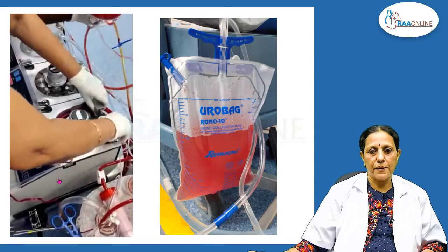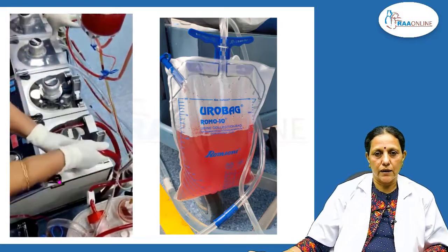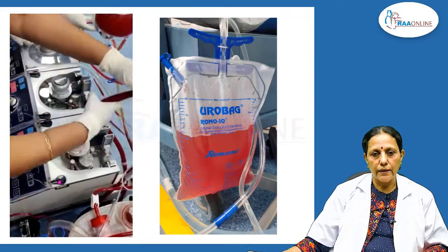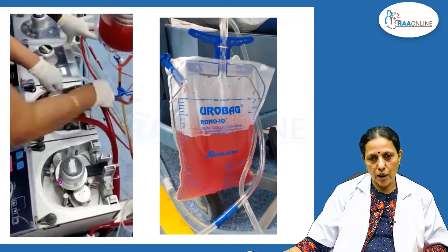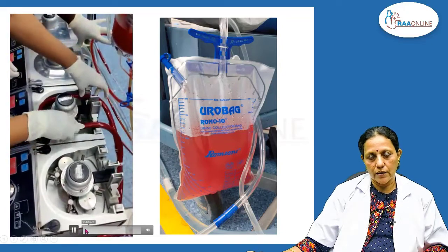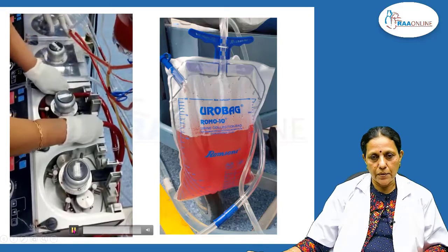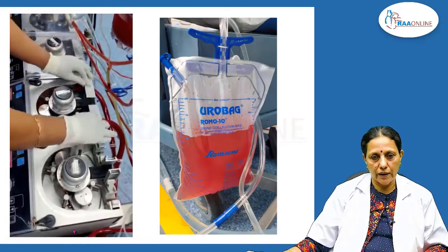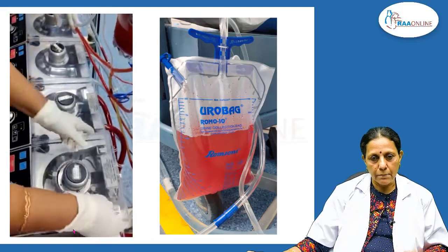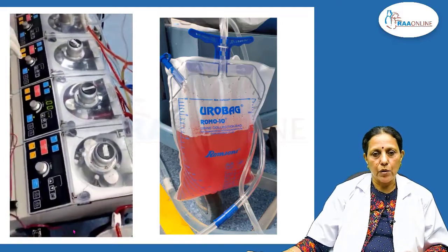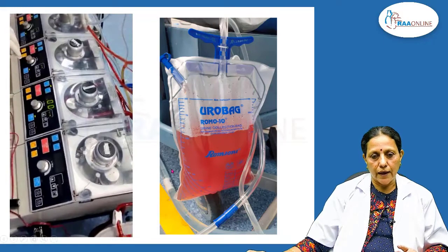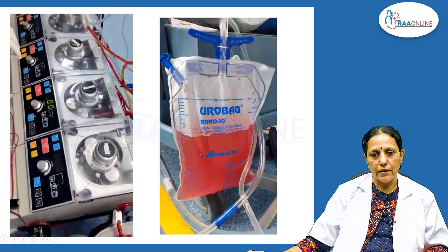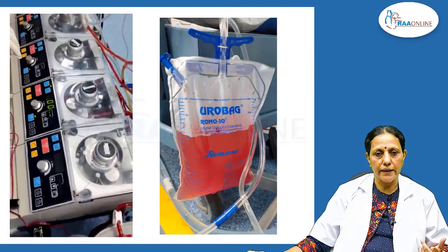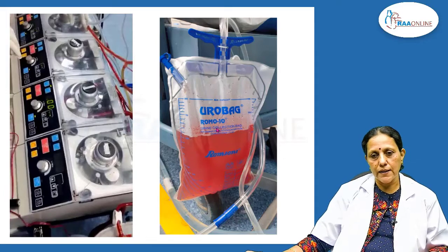Here what happens is, the pump is running. I want to show that this pump has stopped now. So, what I am doing is, I am taking out the tubing. This is the arterial pump. This is how it should be quickly done. This is the arterial pump head. It is taken out and put into the other pump, the next pump. And then you start running. These are the quick methods. By the time the person brings the other pump, this can be done immediately and you can go on bypass.